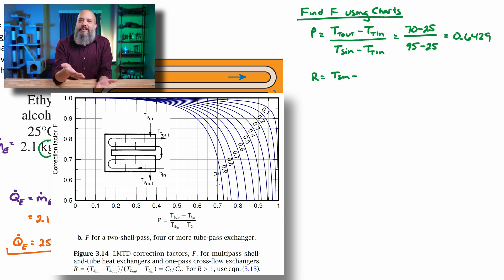And then for R, T_s,in minus T_s,out over T_t,out minus T_t,in, right? This is shell in minus shell out over tube out minus tube in, 95 minus 45 over 70 minus 25 gets a value of 1.111.